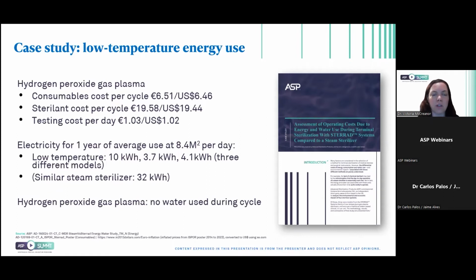This is for one that used 8.4 square meters per day, but a similar sized steam sterilizer would use probably upwards of 3 times as much energy. And of course there's water associated with the use of steam sterilizers, whereas hydrogen peroxide gas plasma sterilizers don't use any water. So while you have this higher cost of consumables, you can potentially trade that off against the electricity and water usage you'd be reducing by using a low temperature sterilizer.